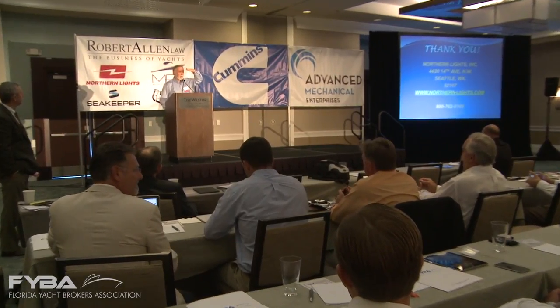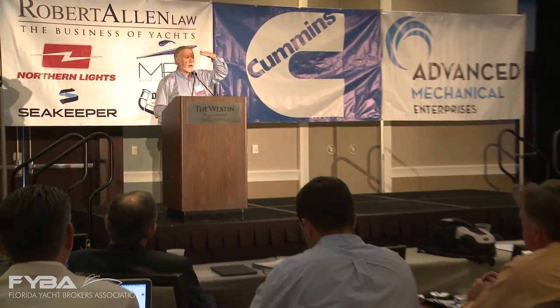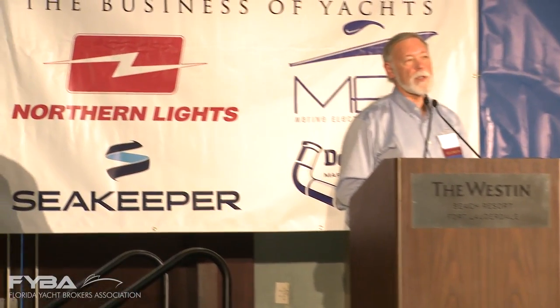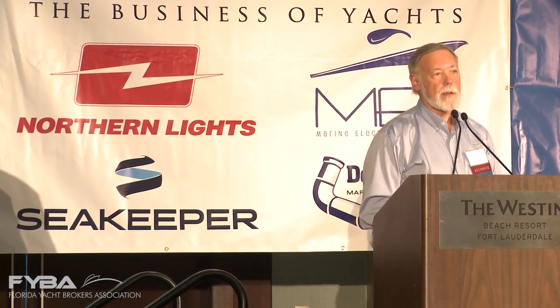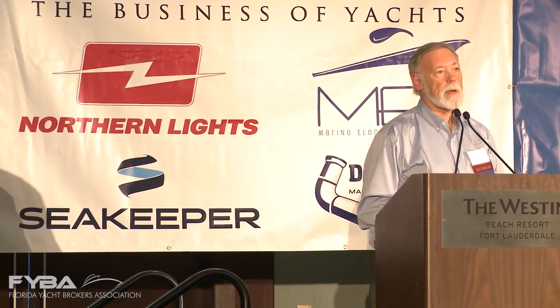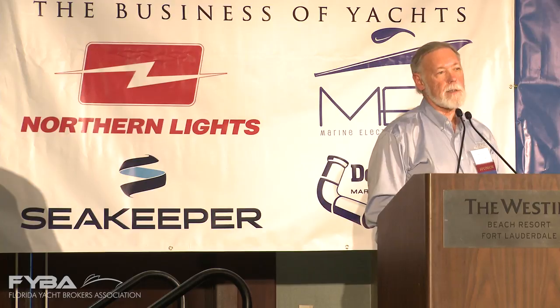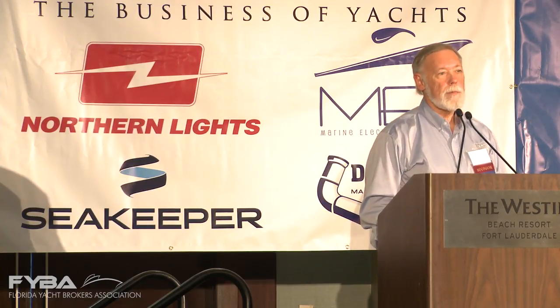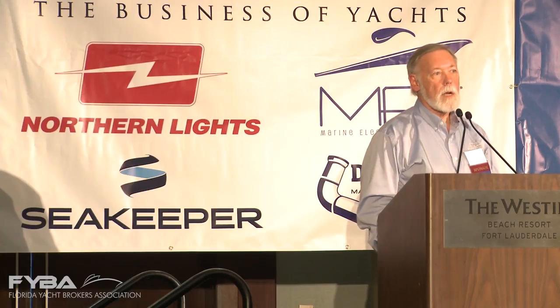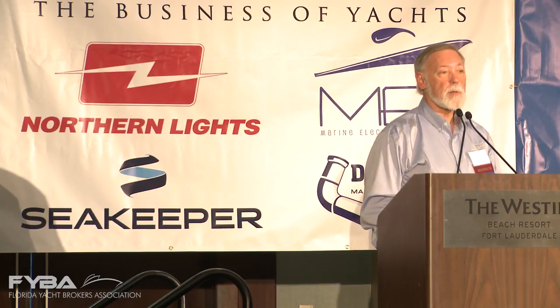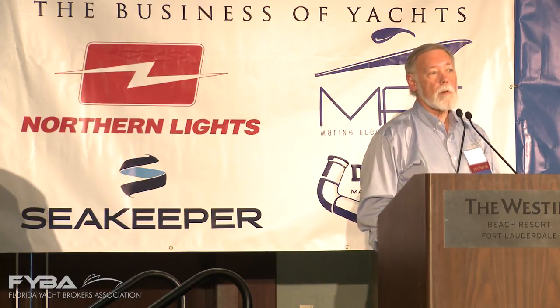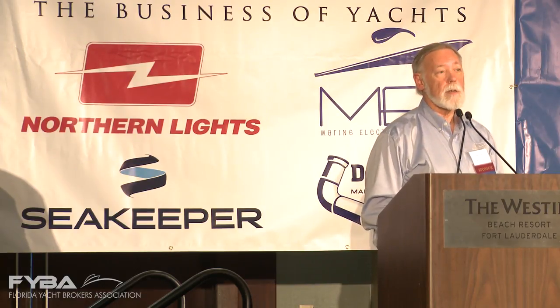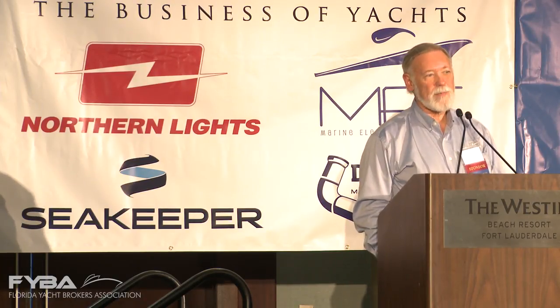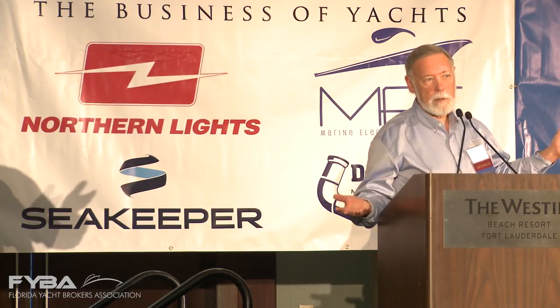Paralleling is possible. On smaller generators though, it's not always desirable because of the cost of the equipment — sometimes the paralleling equipment can approach the cost of the generator itself on small units. In larger units we do it all the time, so it's no big deal. Typically paralleling is done on 50 kW and up machines. A lot of boats now are using smaller generators as a night generator, so that small generator can just be connected to exactly the same bus as the main generator. You just can't run them both at the same time. So yes, you can, but no, you can't.